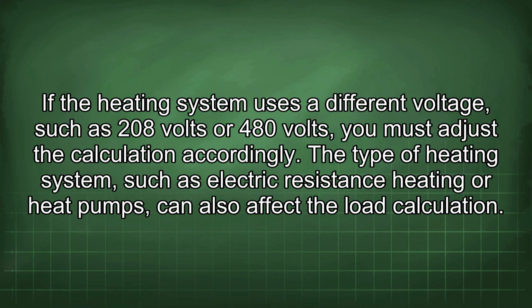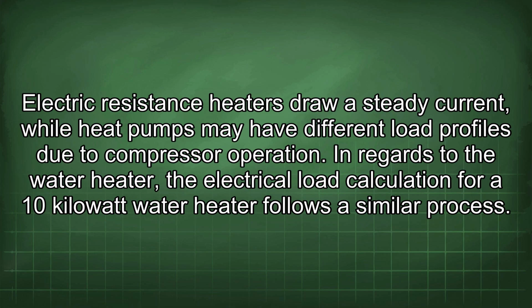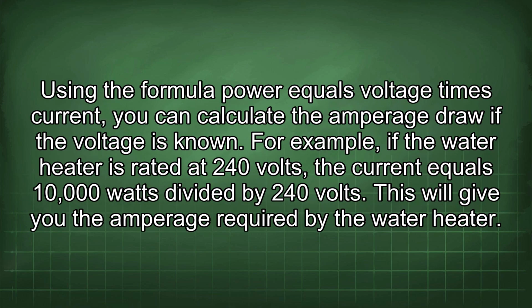If the heating system uses a different voltage, such as 208 volts or 480 volts, you must adjust the calculation accordingly. The type of heating system, such as electric resistance heating or heat pumps, can also affect the load calculation. Electric resistance heaters draw a steady current, while heat pumps may have different load profiles due to compressor operation. In regards to the water heater, the electrical load calculation for a 10 kilowatt water heater follows a similar process. Using the formula power equals voltage times current, you can calculate the amperage draw if the voltage is known. For example, if the water heater is rated at 240 volts, the current equals 10,000 watts divided by 240 volts. This will give you the amperage required by the water heater.